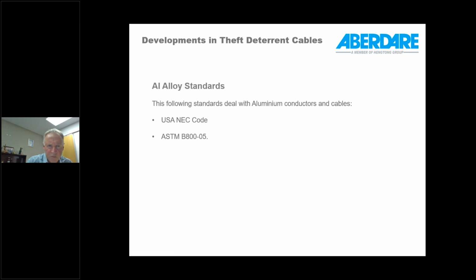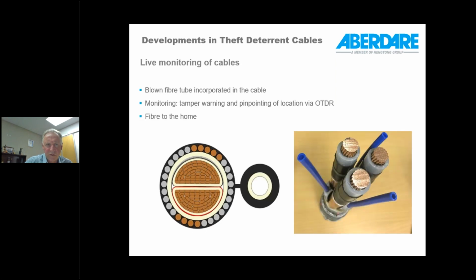But it's well accepted now that these 8000 alloys solve that problem. So the wiring code allows the use of these aluminium conductors without, let's say, any special precautions except for the terminations that are required.